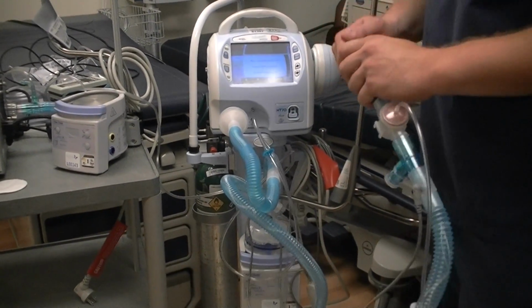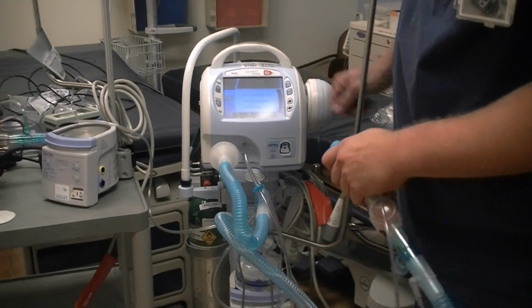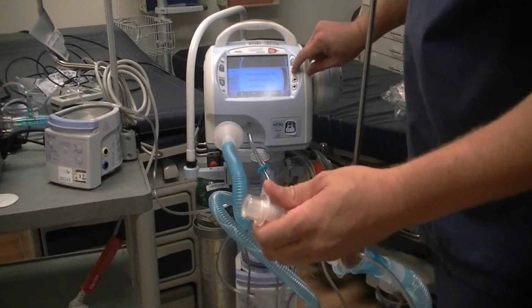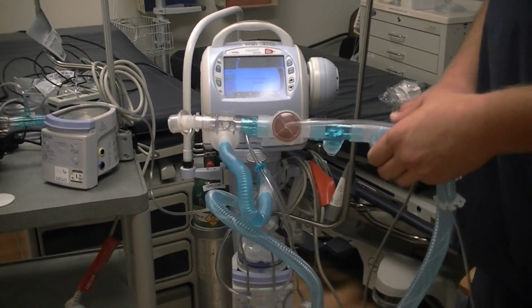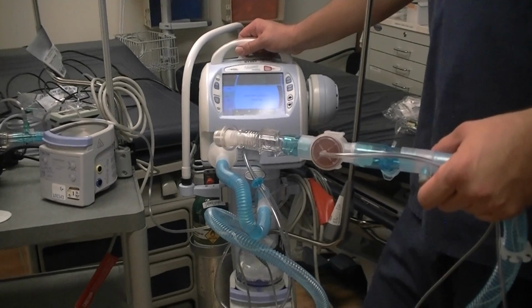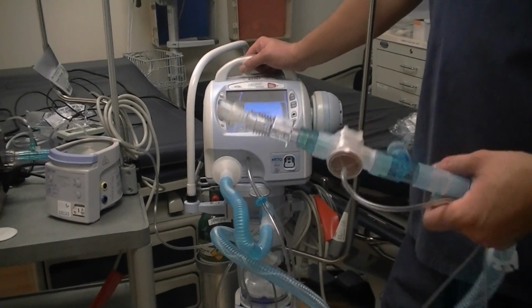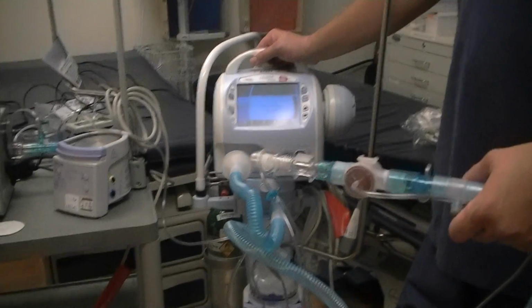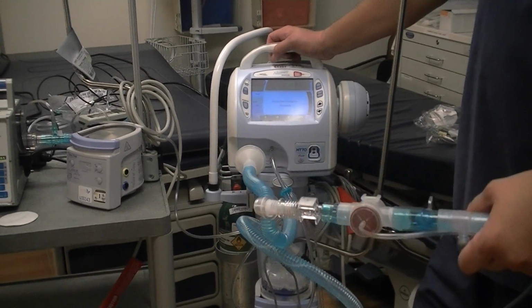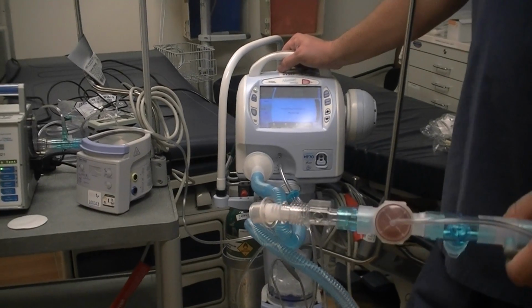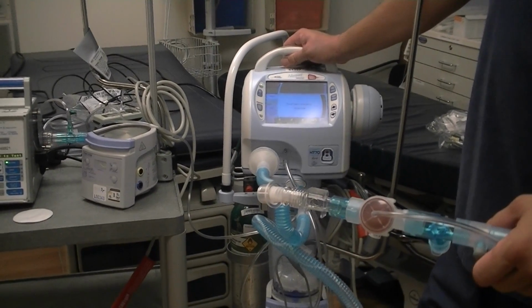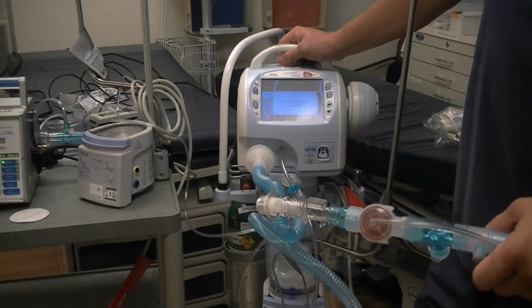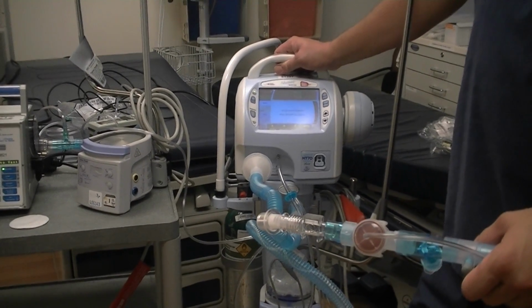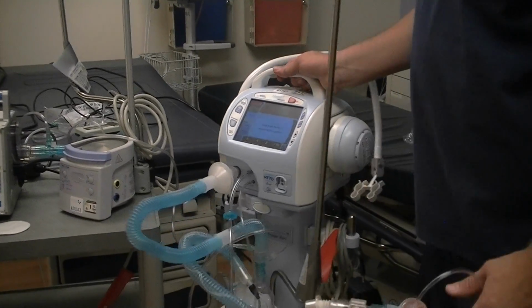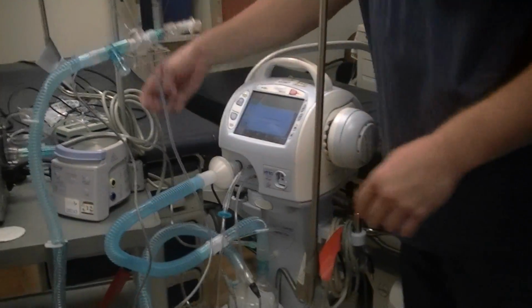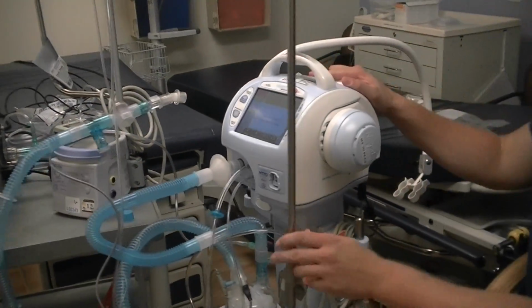Okay, so that time it passed. It says open the patient circuit, press accept to continue. We're going to take our cap off, press accept. You always want to do the calibrations without the suction catheter on. That's the most important. If you leave the suction catheter on, those are more prone to a little bit of leak, it seems like, and they will more often fail your cal. And we're passed.